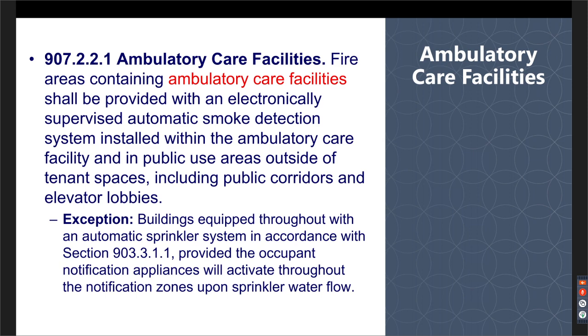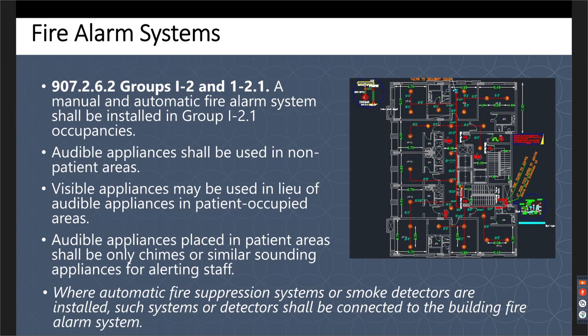I-2.1, a little more specific and a little more restrictive. 907.2.6.2 requires a manual and automatic fire alarm system in all I-2.1 occupancies. I'll paraphrase a lot of this section that says you can use audible appliances or must use audible appliances in non-patient areas, but you can use visible appliances or strobes in patient-occupied areas without audible sounding devices. Audible appliances in the patient areas have to be chimes or a similar sounding appliance for staff alerting. The idea is these patients are incapable of responding to the fire alarm, so we don't necessarily want to alert them or cause them undue fear when the fire alarm system activates. You want to turn that down? Thank you. Where an automatic fire suppression system or smoke detectors are installed, such systems shall be connected to the fire alarm system.